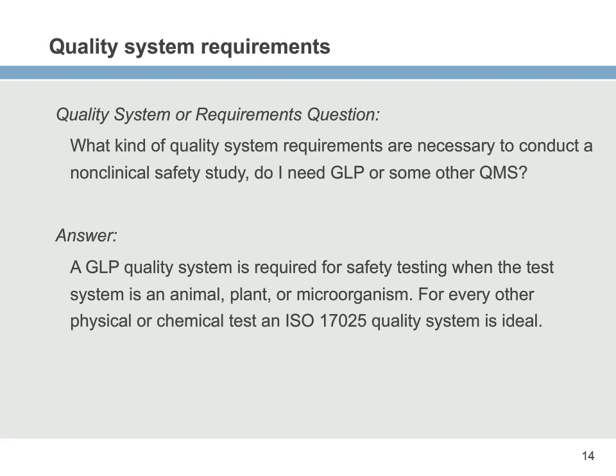A lab performs a GLP test if we can't control or validate the test system. So GLPs are laws that are built around assurance or compliance to the governing QSRs. Then what we use is an ISO 17025 system. This standard is for physical and chemical tests where we can ensure method validation, method uncertainty, and overall measurement repeatability. So the FDA has confirmed that GLP is not intended for physical and chemical tests and is for animal, plants, and microorganisms in correspondence to the GLP updates that are in progress. And you can still claim compliance to GLPs for physical and chemical tests, but in my opinion, the benefits of method validation in accordance with ISO 17025 outweigh GLP compliance.